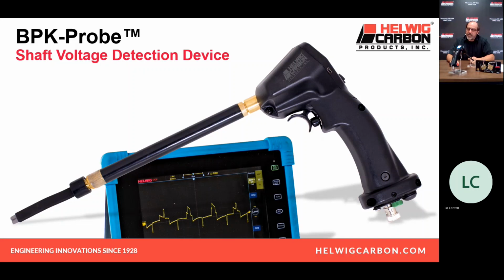Put the probe on the shaft. We can tell you if you're seeing voltage discharges. If you are seeing voltage discharges through your bearing, this will detect and record that data for you. We can measure the risk to the motor. How bad is the discharge, and how likely is it to damage the bearing?